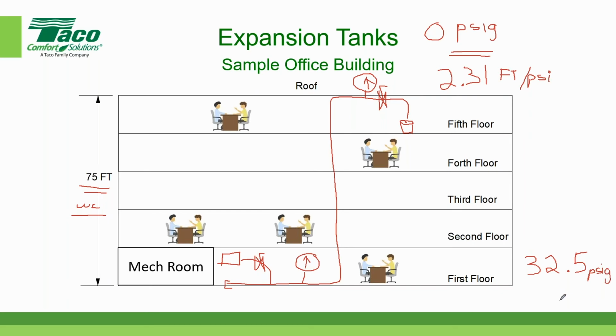Now, here comes the next question. We just said that the pressure at the top was 0 pounds, but we don't want 0 pounds at the top. We want something greater than that. Most people would say they want a pressure at the top of the building somewhere between 5 and 10 pounds. The reason is I want to pressurize the piping system so that if I have an air vent at the top, I have enough pressure to push the air out of the piping. I also want enough pressure at the top to avoid any cavitation that might occur if I had a pump or some other device. So for our example today, to make the arithmetic simple, I'm just going to put in 7.5 at the top of the building.